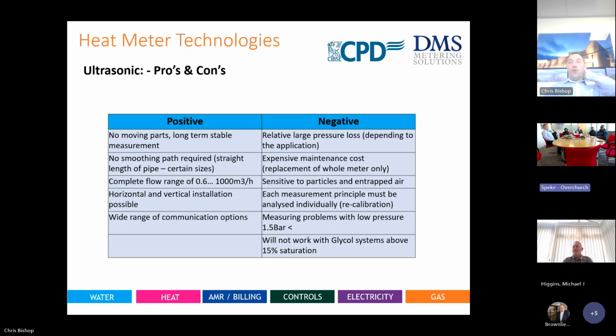Measuring problems. So all meters have to have operating pressures. Ultrasonics do require 1.5 bar or more. If you have situations with a low pressure issue, an end of line district heating system, or a low pressure system as a whole, ultrasonic meters are not the meters to use. You do have to have that operating pressure. Yet again, something you probably wouldn't be aware of. Most systems are probably designed to 2 bar or more anyway, but we put that in our presentation because with anything that was RHI biomass, generally 1 bar was the default. And there are a lot of situations where that meter was just not performing, not delivering the accuracy on the system itself.